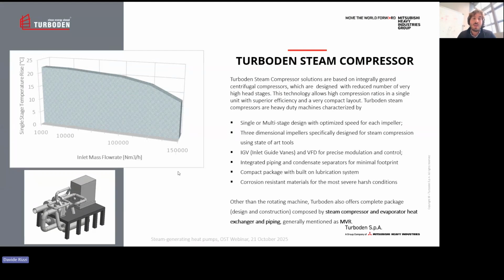Specifically, as you can see on the graph on the top left, we can handle temperature rise per stage up to more than 20 degrees C, and this is possible thanks to the high head of our turbo stages, which are specifically designed for the project and also using special materials. So this is the actual range.